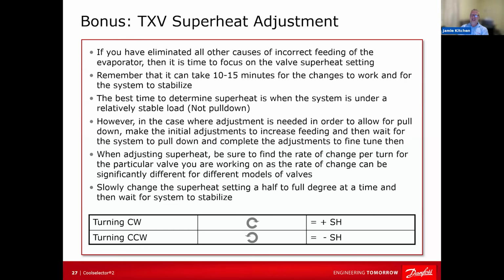Why? What happened? Well, there's a couple of good things here, and we'll start with the TXVs I'm familiar with. If you turn the stem clockwise, you are compressing that spring. So you're increasing superheat, which means the bulb temperature needs to have a greater temperature difference between the evaporator and itself in order for the valve to open up.